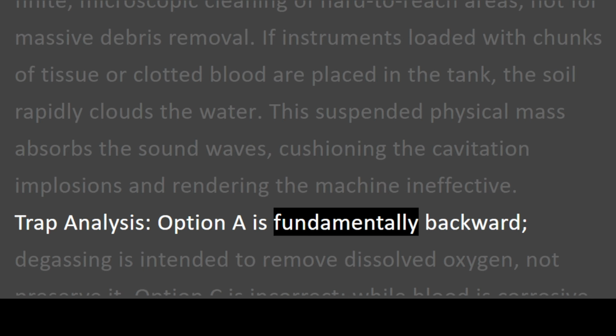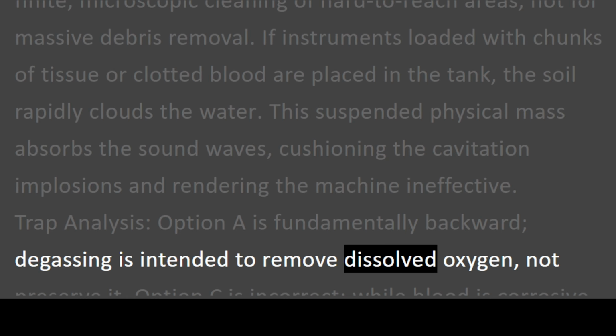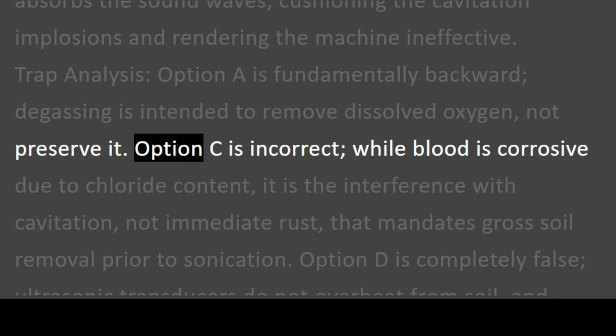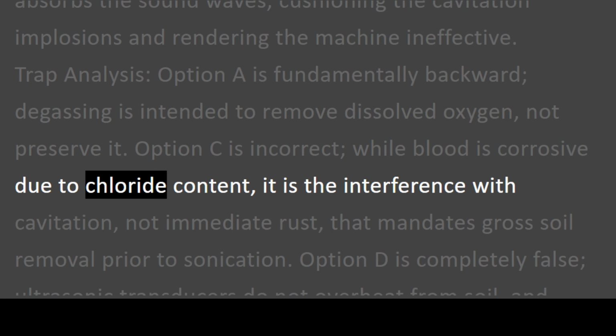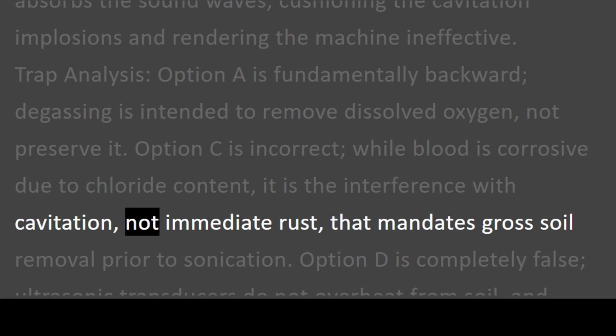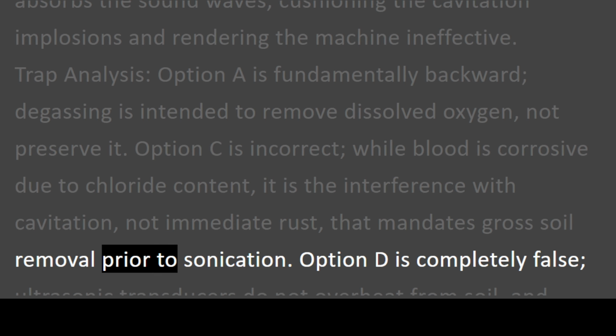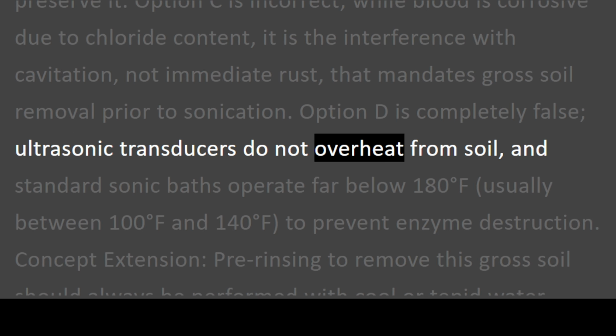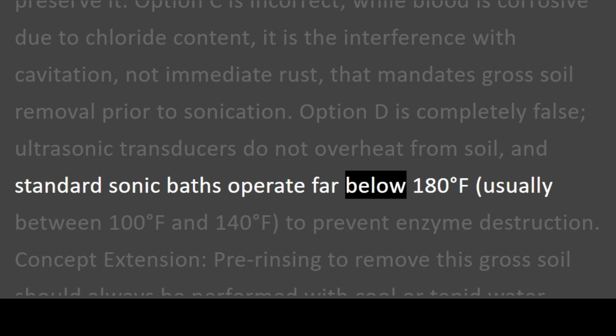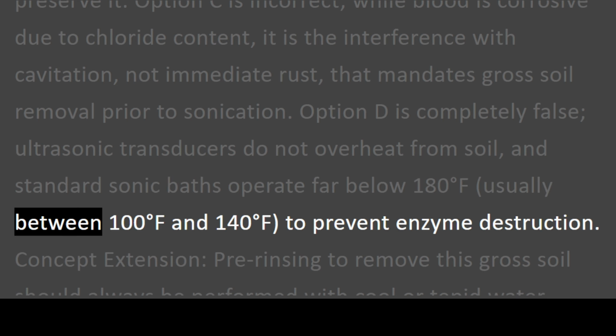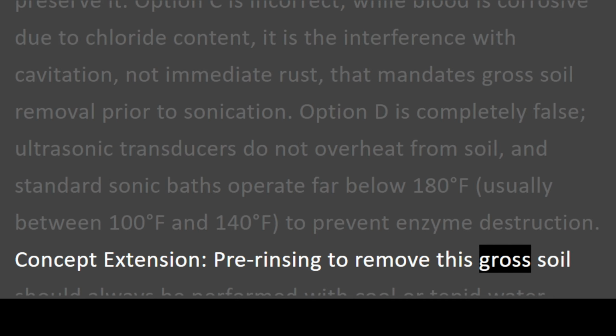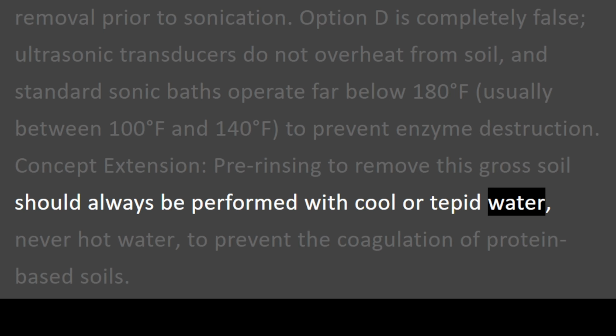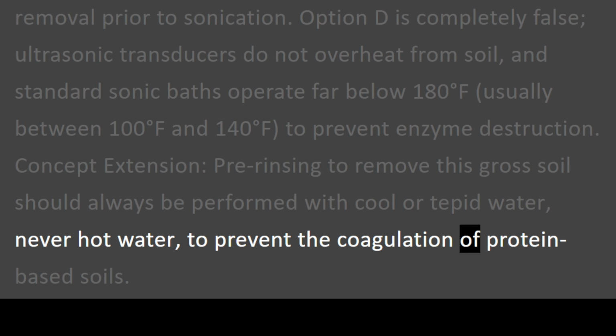Trap analysis. Option A is fundamentally backward. Degassing is intended to remove dissolved oxygen, not preserve it. Option C is incorrect. While blood is corrosive due to chloride content, it is the interference with cavitation, not immediate rust, that mandates gross soil removal prior to sonication. Option D is completely false. Ultrasonic transducers do not overheat from soil, and standard sonic baths operate far below 180 degrees Fahrenheit, usually between 100 degrees Fahrenheit and 140 degrees Fahrenheit, to prevent enzyme destruction. Concept extension. Pre-rinsing to remove this gross soil should always be performed with cool or tepid water, never hot water, to prevent the coagulation of protein-based soils.